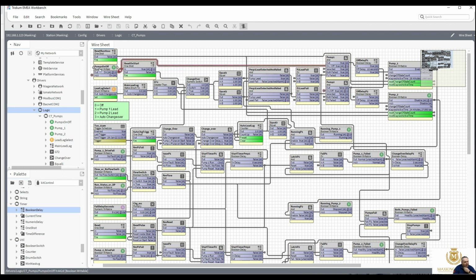When you switch your boilers off, that would normally go off, but what we're doing, what will happen now, sorry about that, bloody background thing running there. Anyway, yeah, we can have a situation where that turns itself off for the boilers, so the boilers turn off but the pumps carry on running, and you can set that to say 5 minutes, and it would just get rid of all the excess heat in the heat exchanger.